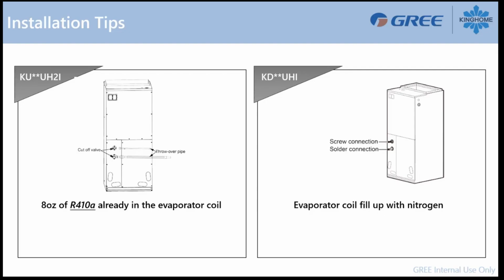Also, another big difference between those two is the KU comes already with R410A refrigerant inside the coil. So you have about 8 ounces of refrigerant already in the coil. Except the KD doesn't have this refrigerant inside of it, it's filled up with nitrogen. So just make sure you purge this coil, when we're talking about the KD, before you do your braze connection. And also make sure the system will be refilled correctly after you have done your full installation.